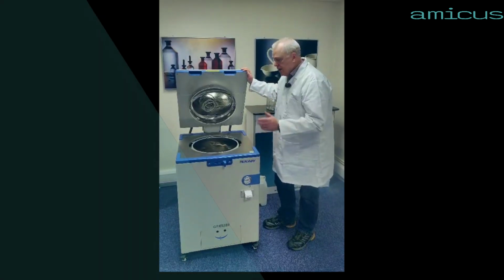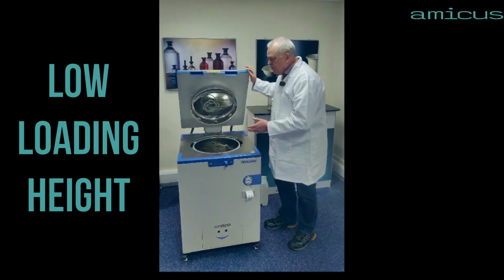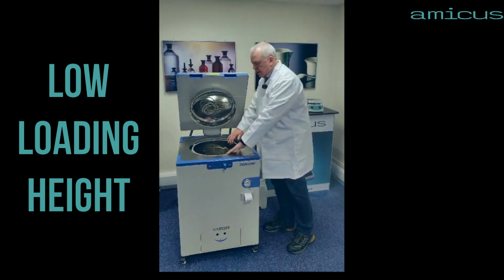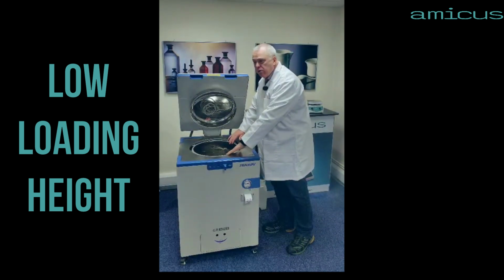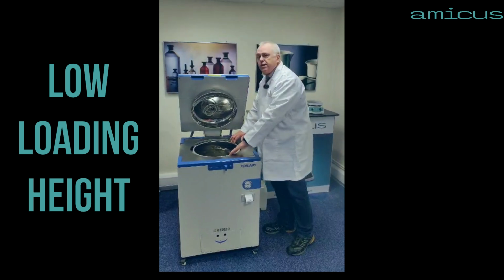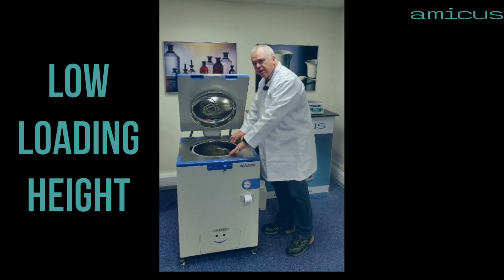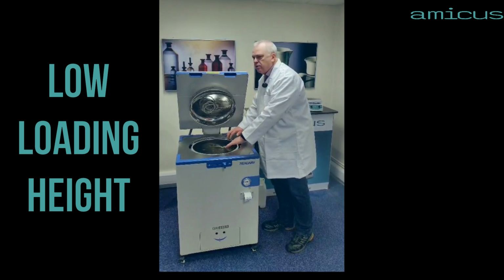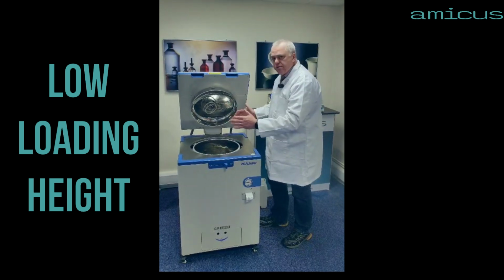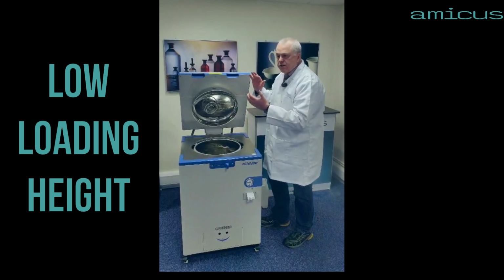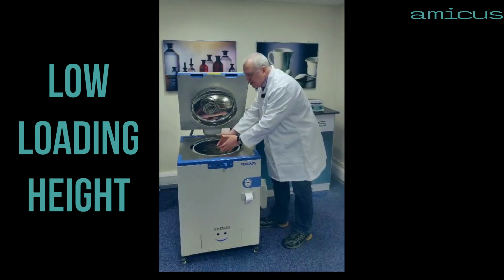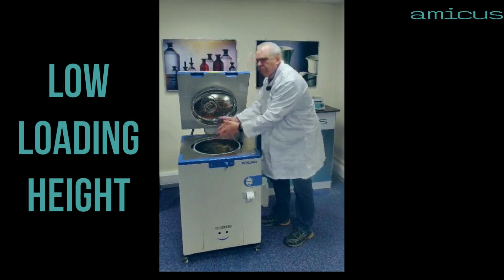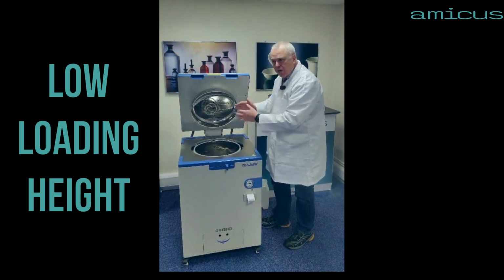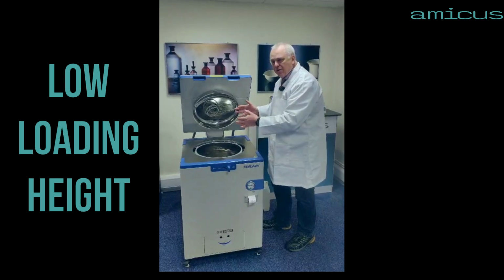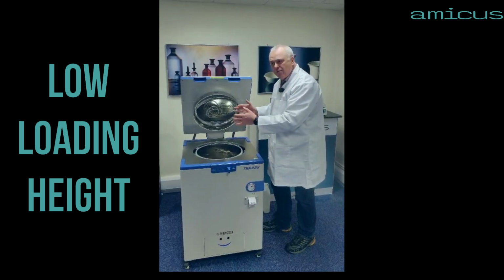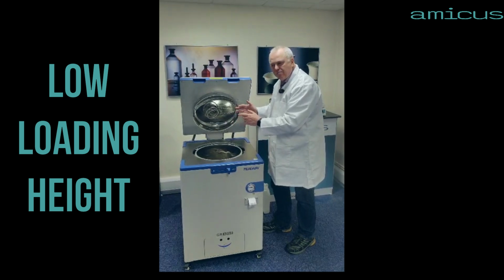They appreciated the low loading height, which is achieved by having a slightly wider diameter chamber than most autoclaves of this size. This is a 60 litre machine. The 85 litre is very similar. Because of the extra width, the extra diameter, you have less depth. So you have a nice low loading height, which makes it easier to get into the machine. And it also means you make better use of the overall capacity. So in effect, you have a larger machine than you would have with a comparable 60 litre machine.